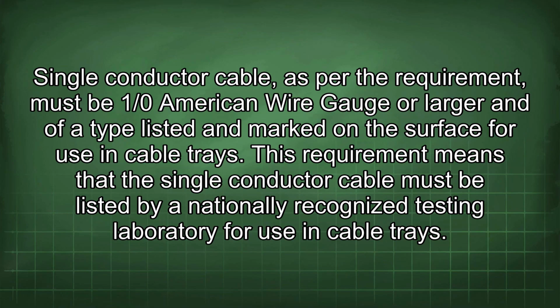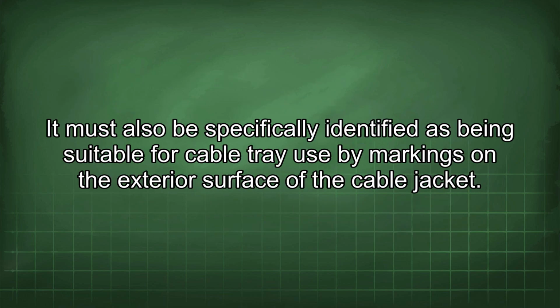Single conductor cable, as per the requirement, must be 1/0 American wire gauge or larger and of a type listed and marked on the surface for use in cable trays. This requirement means that the single conductor cable must be listed by a nationally recognized testing laboratory for use in cable trays. It must also be specifically identified as being suitable for cable tray use by markings on the exterior surface of the cable jacket.